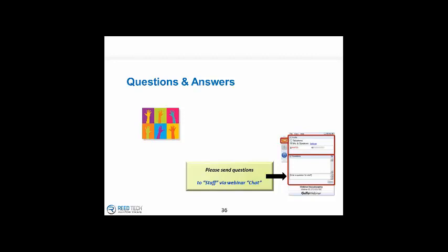All right, very good questions. So when you are submitting by way of SPL, the only field that is submitted is the actual GMDN code, and we'll talk about one alternative in a second. The actual description and the term itself are two of the fields that the FDA does a lookup because they have access to the GMDN dictionary, and they do a lookup based on the submitted code and provide that as part of their database. So only the GMDN code is submitted for the first part of that answer.